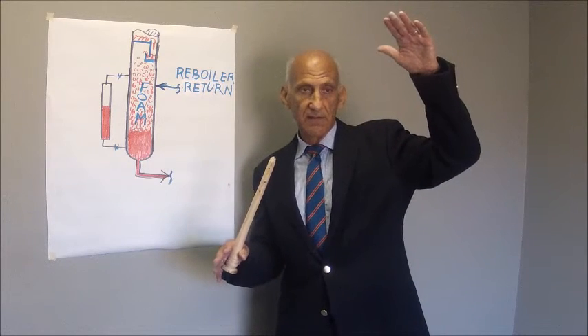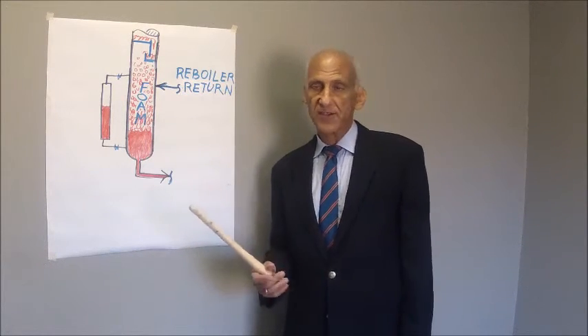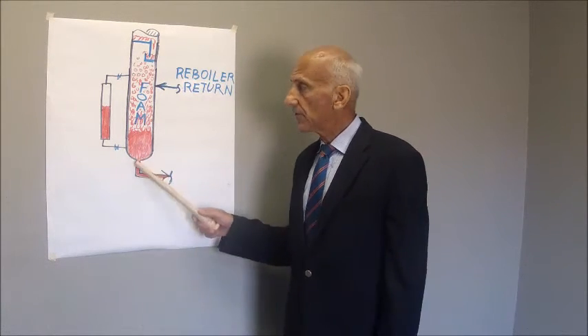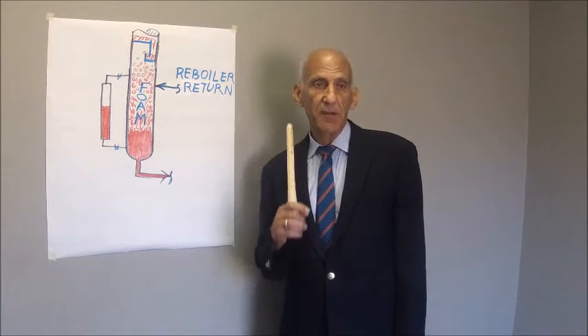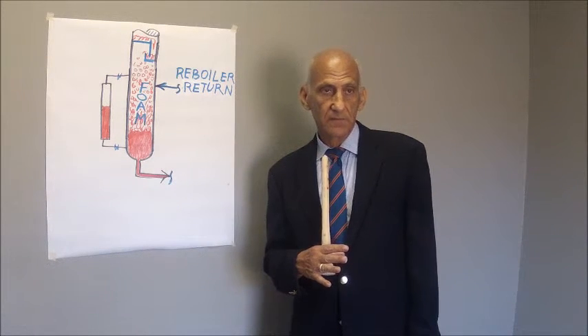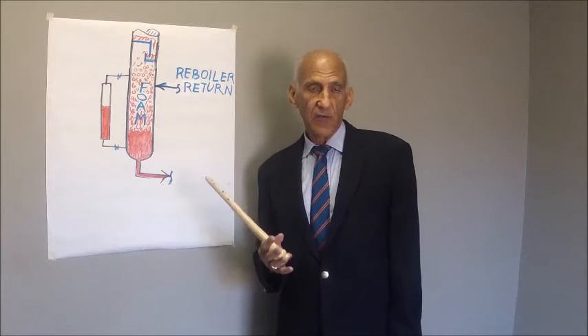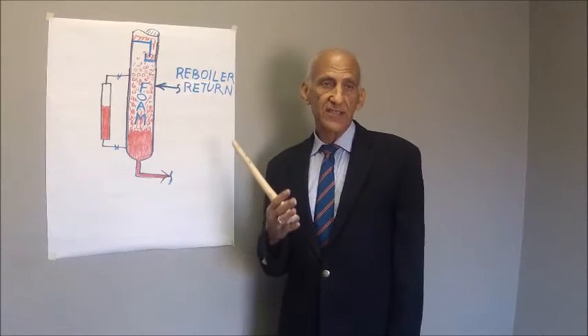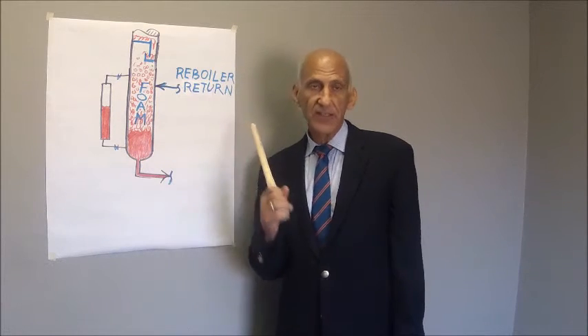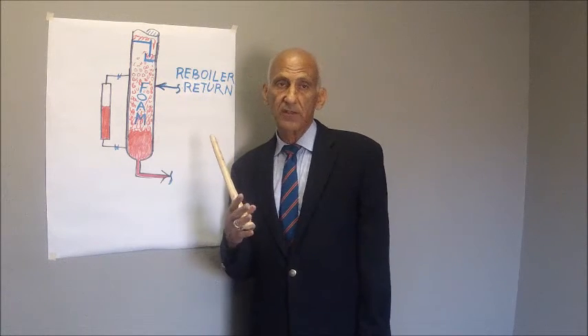Actually, I've seen it from 90% to 10%. But let's just say, for the sake of illustration, the foam density on average is 50% of the clear liquid density. Then even though the foam is above the top tap of the level glass, we'll only have half the level glass full of clear liquid. Really, one should not call this a level glass at all — it's a gauge glass, in the sense that it is measuring the pressure difference between two points in the tower, in terms of the specific gravity of the liquid in the glass and not the liquid or foam in the tower.